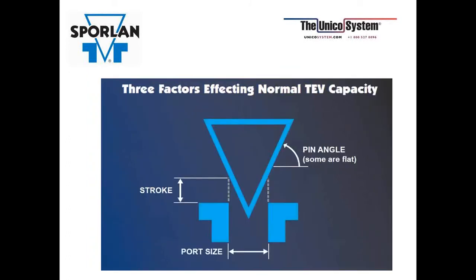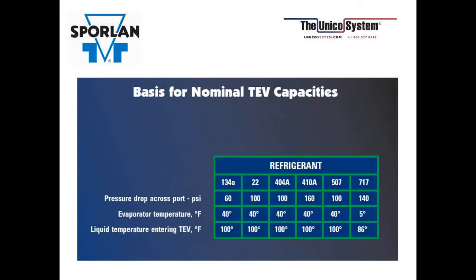There are three factors affecting the normal TEV capacity: the port size, the stroke, and the pin angle. If you change any one of those when we're designing valves, it's going to change the nominal capacity of the valve. And for us, the basis for the nominal capacity, using R22 and R410A, you notice the parameters we use for nominal capacities are an evaporator temperature of 40 degrees and a liquid temperature of 100 degrees. For R22, we use a pressure drop across the port of 100 psi, and for R410A, we use 160.